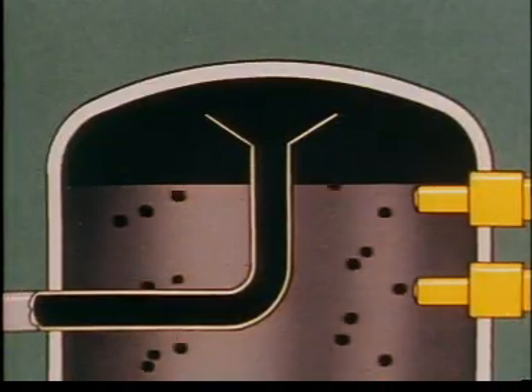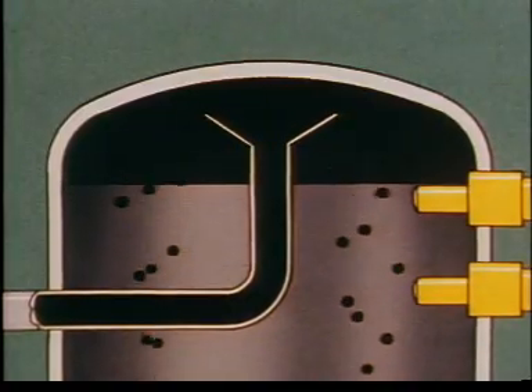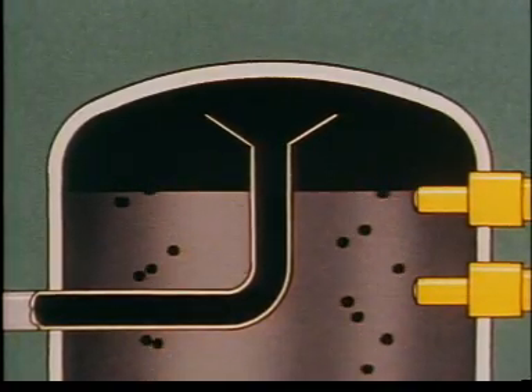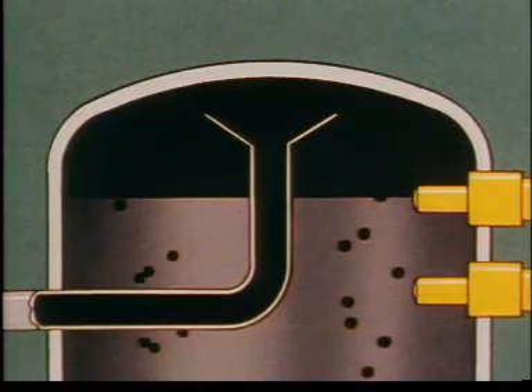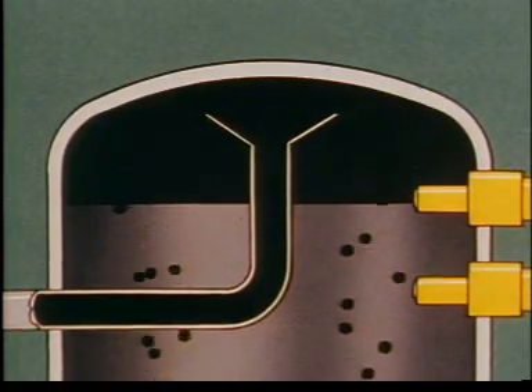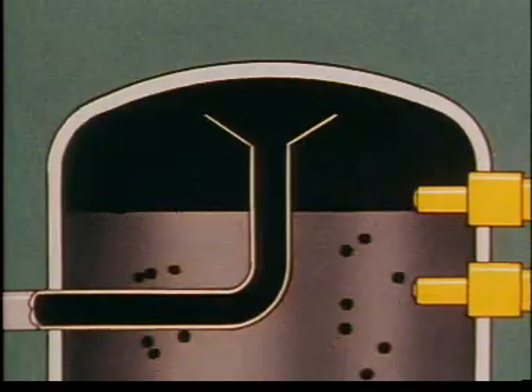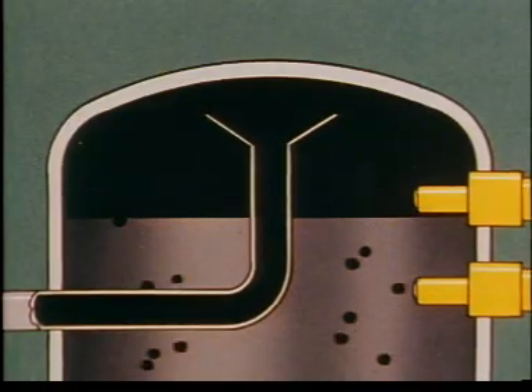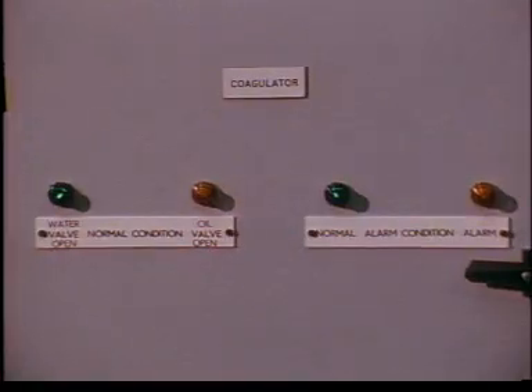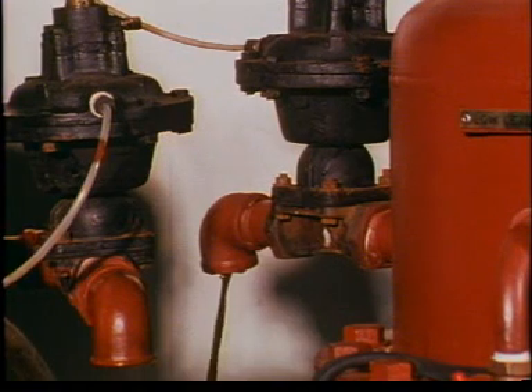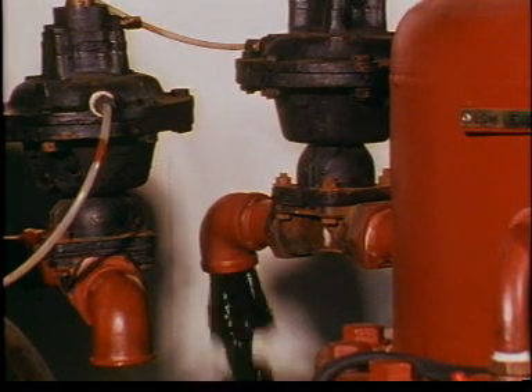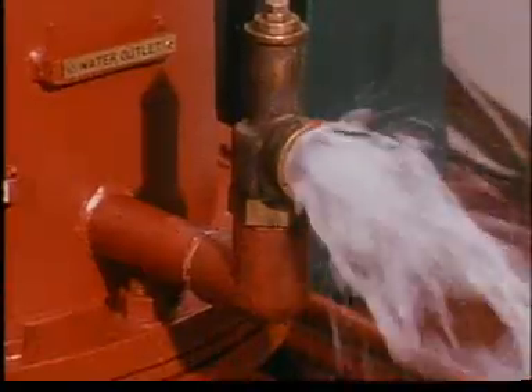Since there is so much less oil in the liquid compared with that in the separator, the level of the oil-water interface falls very slowly, so that 2 separate operating probes are not necessary. When the upper probe is completely covered with oil, an oil indicator light is illuminated on the control panel for the high-level probe, and the oil outlet valve opens and allows oil to be drained to the storage tank.